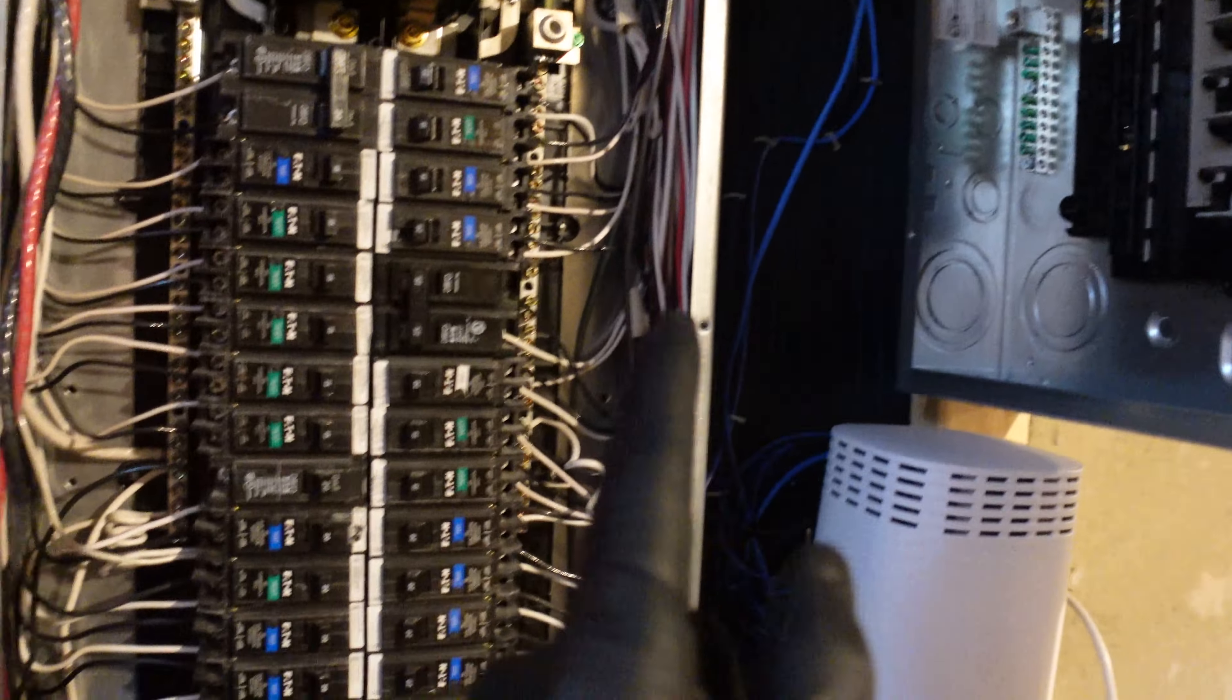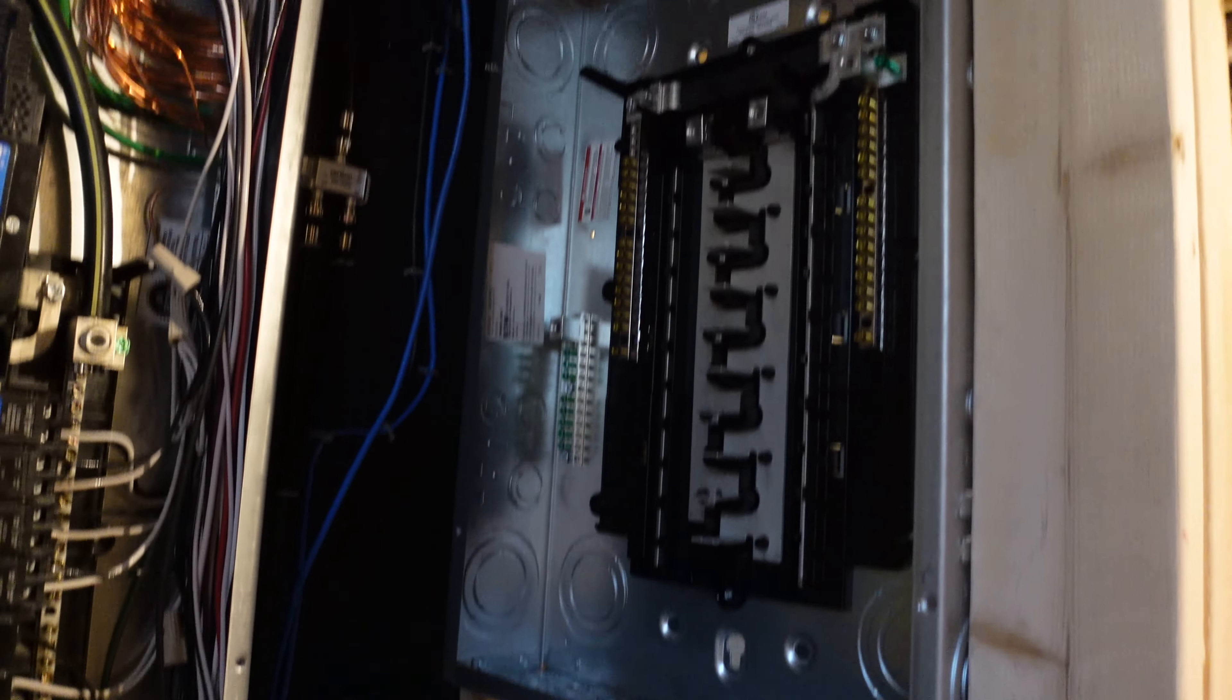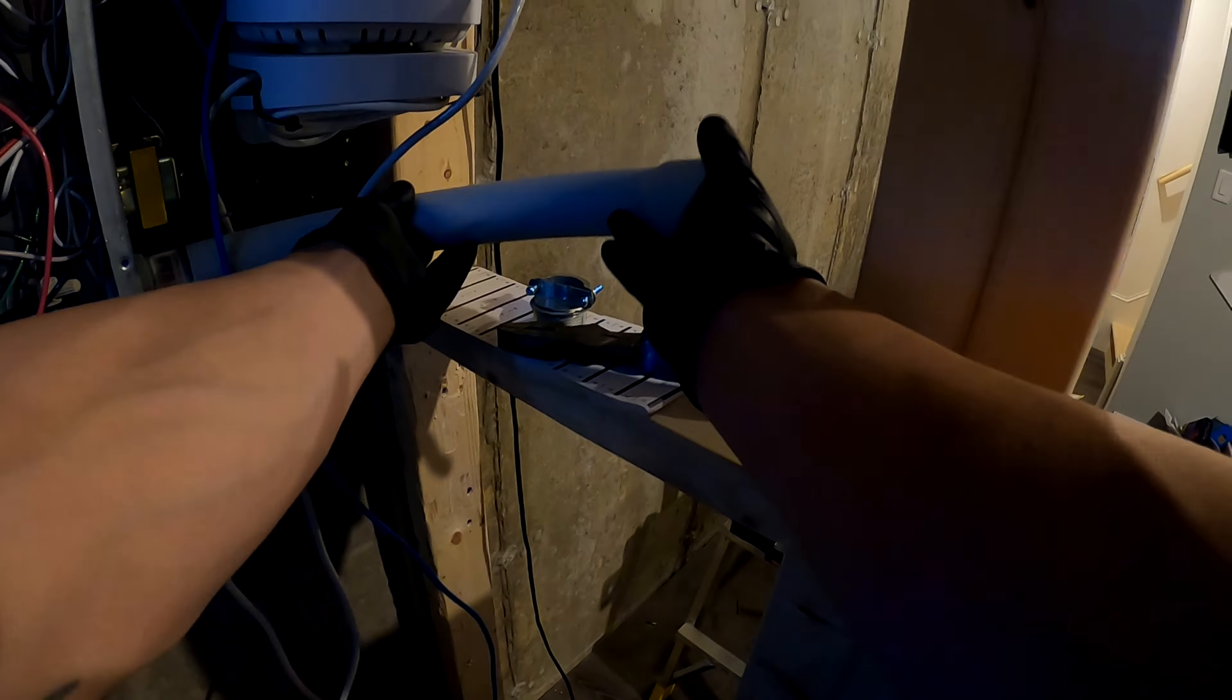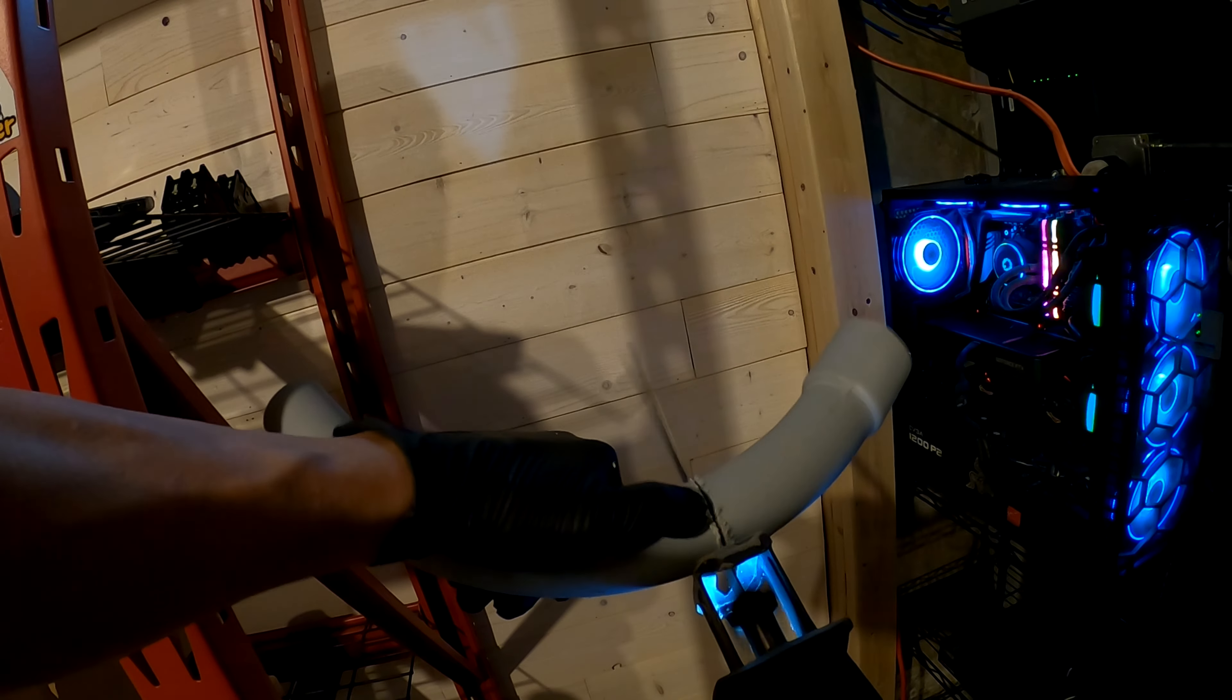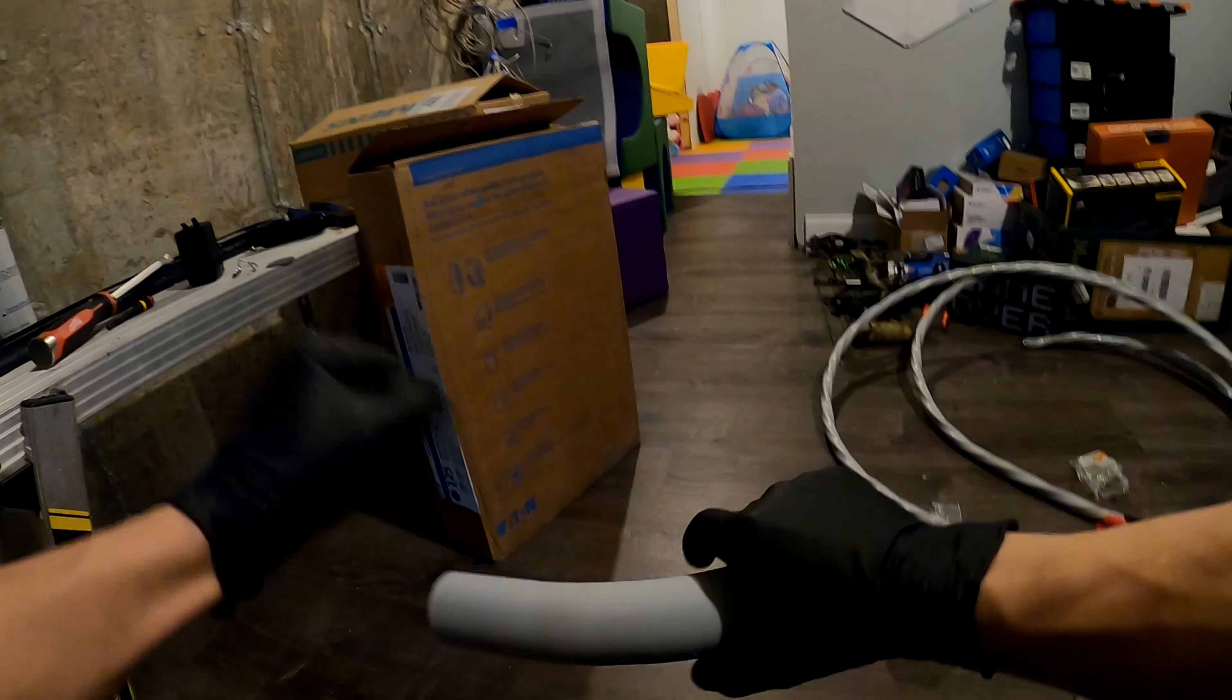So my plans here are to basically run a tube from this knockout spot right here, if I can down and into the bottom of this panel right here. So let me take this out. I'll show you. All right. So if you look right here, I have a knockout. That's the one I'm going to punch out. I have rubber gloves on just in case. I don't know. Maybe might help me. Who knows? Probably not. But I do need to shut off the power to the entire house. As you can tell, it's still on. So this is going to get dumped when I'm ready to do so. But for the time being, I'm going to throw this cover back on. I'm going to get this wired up. Obviously I have to strip this right here, get these four wires. If you can see them right there fed into the bottom of this panel, try to get the PVC all done and go from there. So what I'm going to do is set up my GoPro and I'm just going to speed through it. Let's see what we can do.